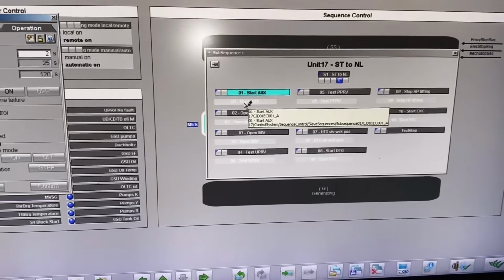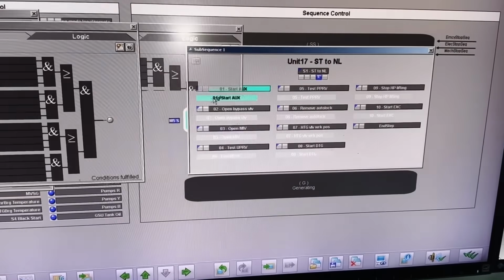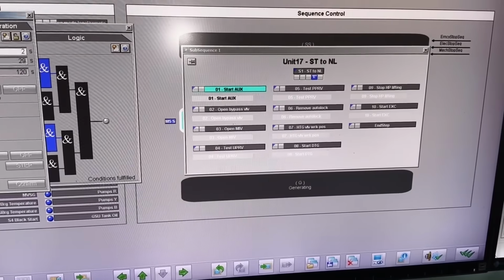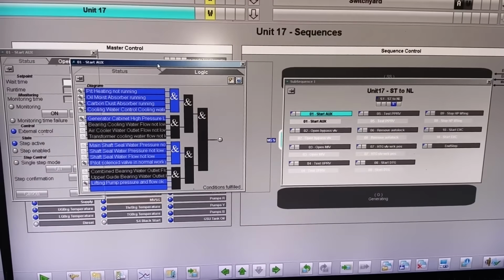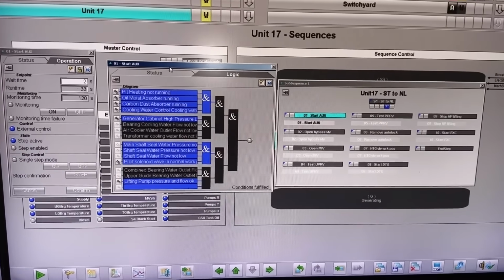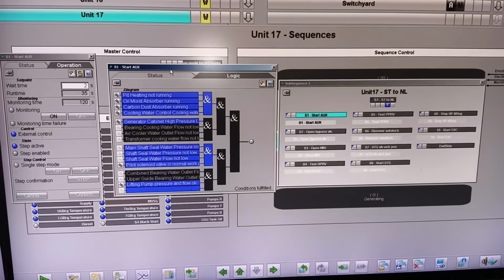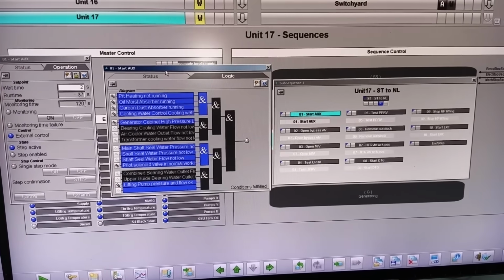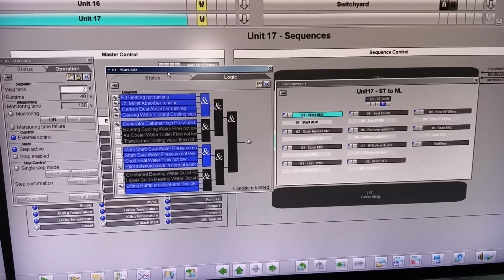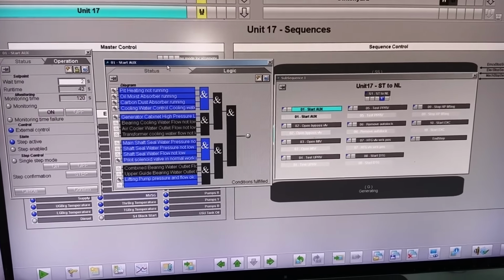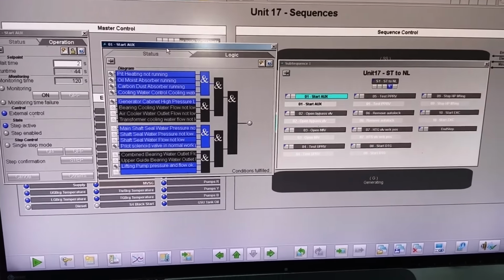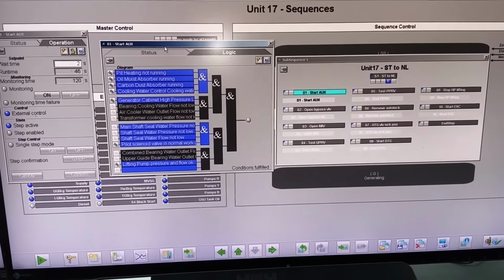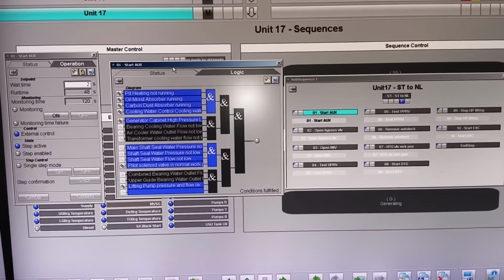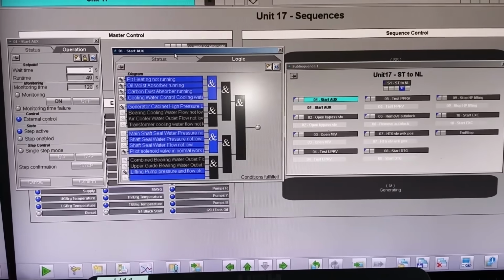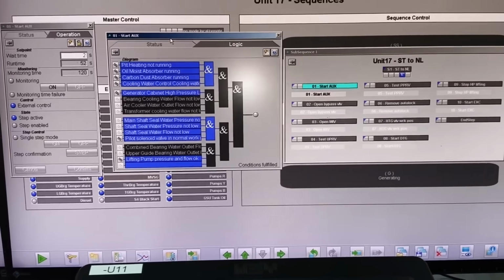At this moment, the turbine runner, generator, rotor, and main shaft are completely stationary. And interestingly, the first priority is not generating electricity; it's protecting the machine. And before this unit can even move, the automation system starts a long checklist of auxiliary systems. For example, lubricating oil pumps, cooling water circuit, shaft seal water system, moisture removal system, and bearing cooling arrangement, carbon dust extraction system, and high pressure oil lifting pumps.